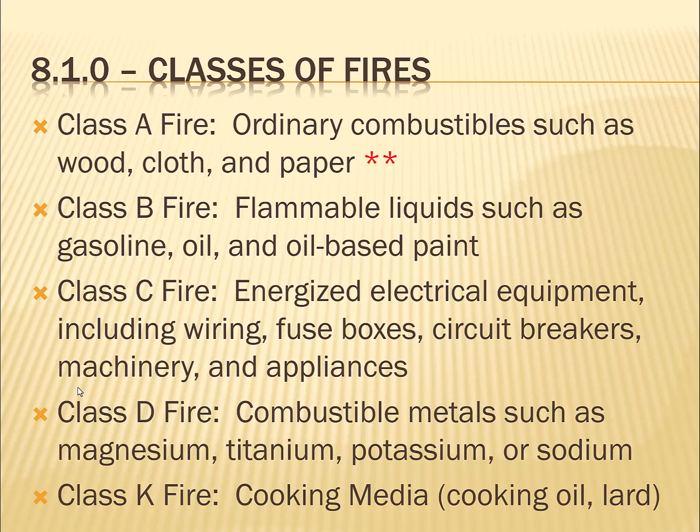Class C, you can't use water either because it could conduct right back through the stream of your garden hose or your fire hydrant hose. So Class C fires, you don't use water either. So look at that. Okay, so there are special fire extinguishers for each one of these fires, although the most common fire extinguisher for people to have, the one that you might have around handy, and the one that you probably should have on your site, would be rated for all three, for Class A, B, and C fires.